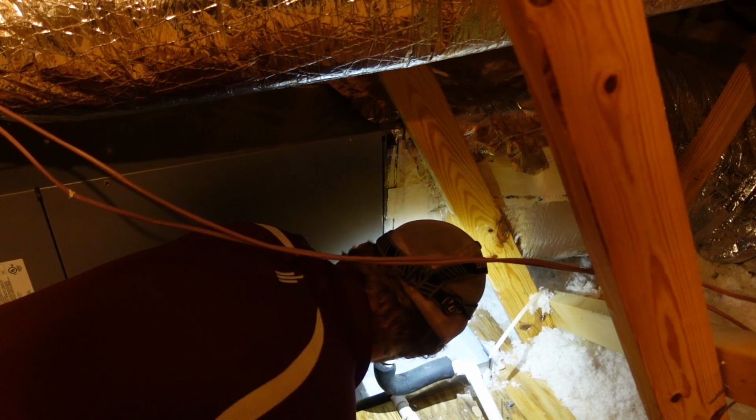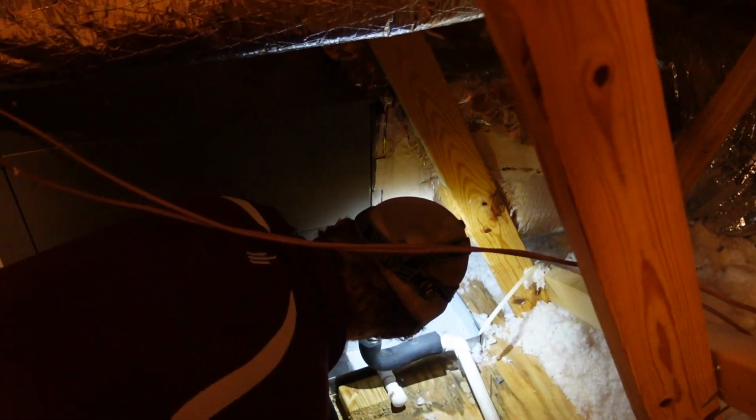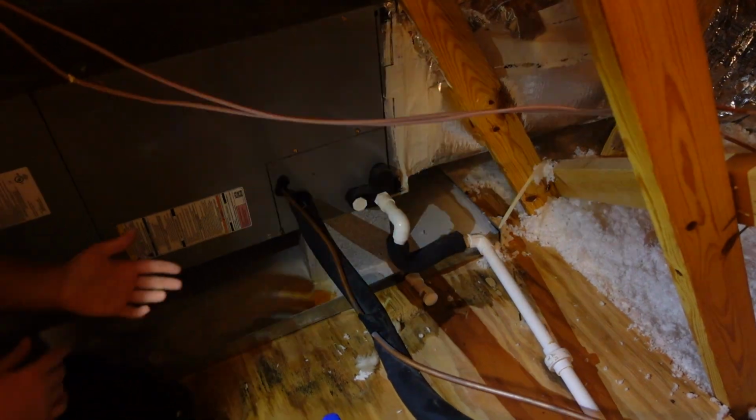Number three, check your drain. So in homes, especially if you have a system that's located in the attic or in a closet, check your drain, check around the unit, see if you see any moisture present. It could be that your emergency drain pan has filled with water, and this could be causing a wet switch or drain switch of some sort to keep the system from functioning. The primary cause would be a clogged drain, so that drain needs to be cleaned, and then the switch reset so that your system can function properly.